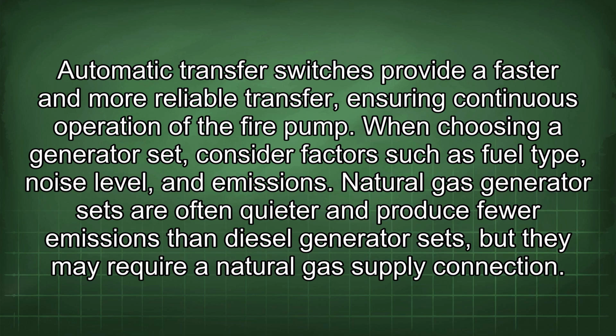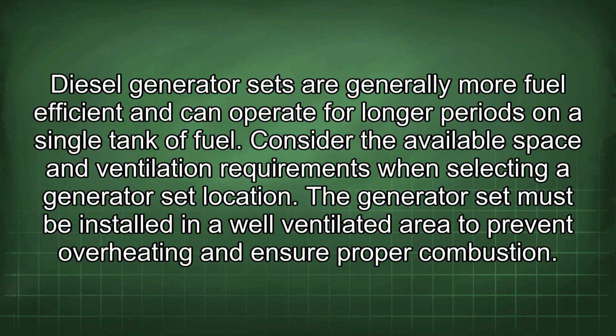When choosing a generator set, consider factors such as fuel type, noise level, and emissions. Natural gas generator sets are often quieter and produce fewer emissions than diesel generator sets, but they may require a natural gas supply connection. Diesel generator sets are generally more fuel efficient and can operate for longer periods on a single tank of fuel. Consider the available space and ventilation requirements when selecting a generator set location.